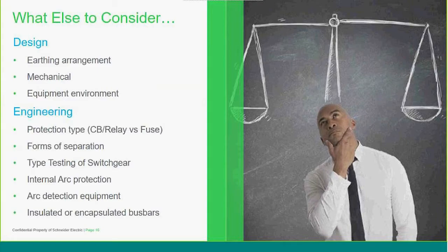There's lots of other things that we need to consider. The earthing arrangements on site, to ensure we again try and get faster clearance times for all different fault scenarios, the mechanical design of the substation, the mechanical design of the equipment, trying to remove our risk. As I mentioned before, for medium voltage switchgear, the standard talks about certain arc flash performance ratings. We talk about AFLR, arc flash front, lateral and rear. So no matter which zone you're stood in, you're covered, and that's an element to think about in designing new equipment.